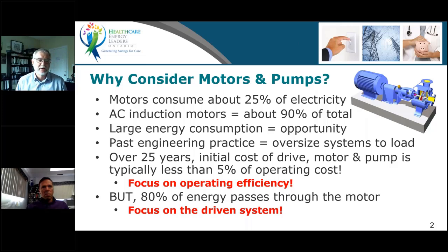We need to go back and right size. I think in energy, right sizing is one of those areas where it makes a lot of sense, with considerations like not dropping your pressure too low as in a boiler, and the same thing can occur in pumps too, or an analogous situation. The last 2 points here I think are important. Over 25 years, if you look at the 25-year life of a motor and pump system, the initial cost of a drive, motor, and pump is typically less than 5% of the energy operating cost, or the operating cost of that particular system. So that really asks us to look at operating efficiency.